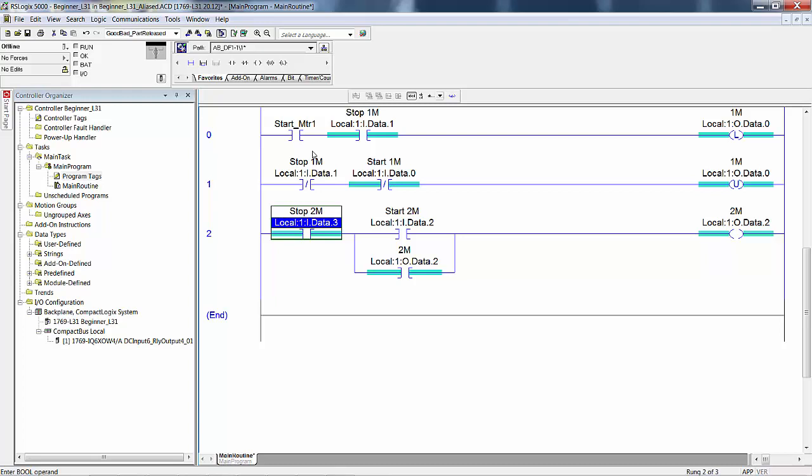The ladder logic diagram will execute the same regardless of which database the tag is in. But if we want to reuse the program, we need the tags isolated from all of the other programs, and we do that by creating or moving them into the program tags database.